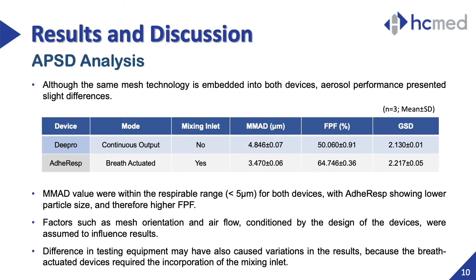In this table, you can see the mean values with standard deviation for the parameters from the APSD study of both nebulizers. The mixing inlet was not used in the NGI test of the continuous output nebulizer while it is required for the breath-actuated one. For both devices, the MMAD values were within the respirable range, which are favorable to deep lung deposition. ADHERESP generated droplets with smaller mean particle size, leading to a higher percentage of FPF, despite presenting a slightly higher GSD than Deepro. Although the embedded mesh technology is the same for both devices, different orientation of the mesh membrane and the structure of the medication reservoir were assumed to influence the results, along with the difference in testing equipment setup.